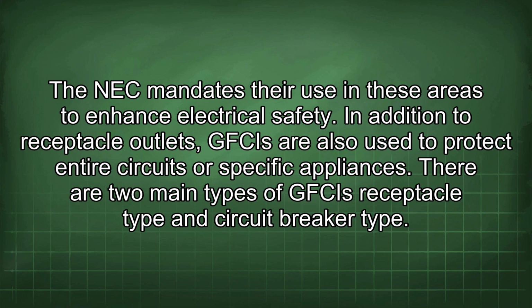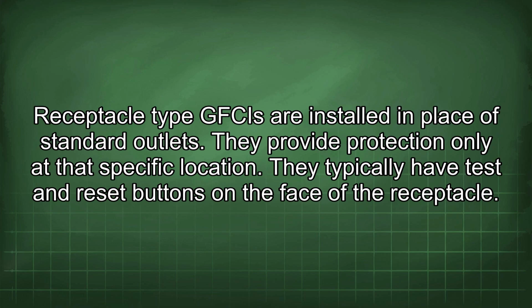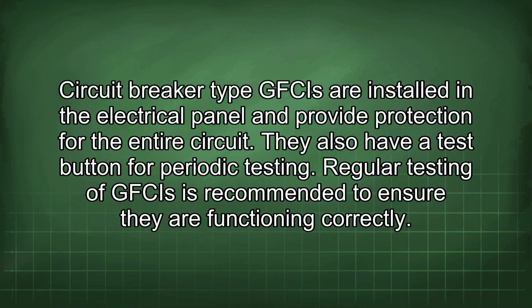In addition to receptacle outlets, GFCIs are also used to protect entire circuits or specific appliances. There are two main types of GFCIs: receptacle type and circuit breaker type. Receptacle type GFCIs are installed in place of standard outlets. They provide protection only at that specific location. They typically have test and reset buttons on the face of the receptacle. Circuit breaker type GFCIs are installed in the electrical panel and provide protection for the entire circuit. They also have a test button for periodic testing.